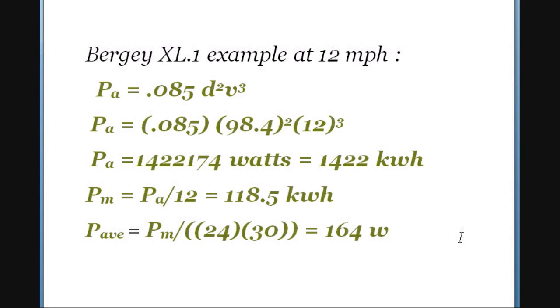Let's take the Bergey unit from the last lesson as an example, and see what it would do at 12 miles per hour. Taking the formula, plugging in the rotor diameter of 98.4 inches and a wind velocity of 12 miles per hour, and multiplying it out gives 1,422,174 watt-hours, which is 1,422 kilowatt-hours per year. So if you have a Bergey unit and a 12 mile-per-hour average wind, it'll generate 1,422 kilowatt-hours in a year, assuming your installation is compatible with that 12 mph condition.